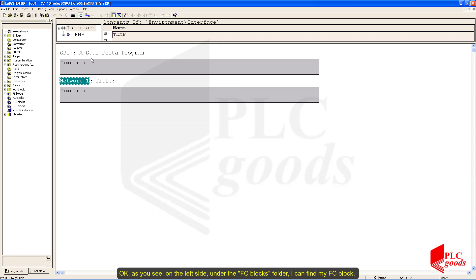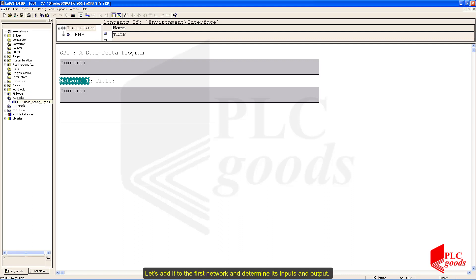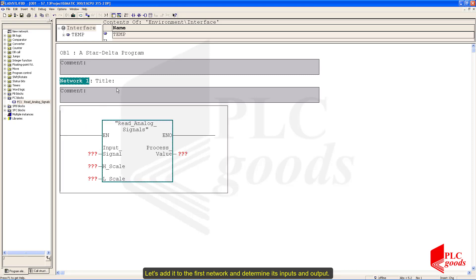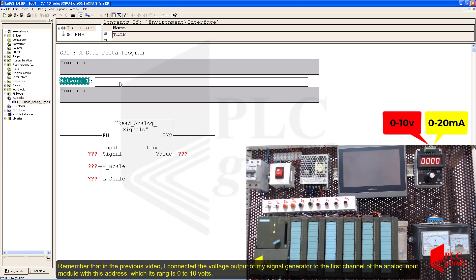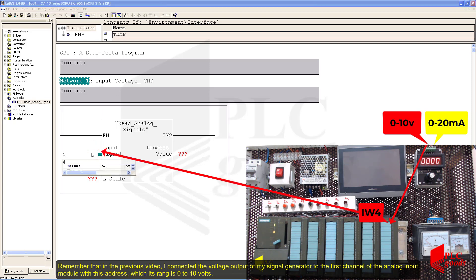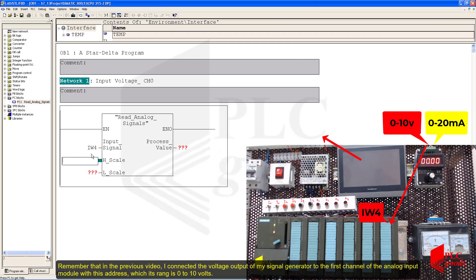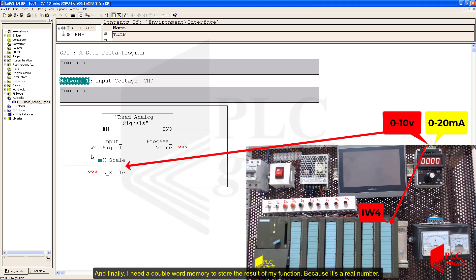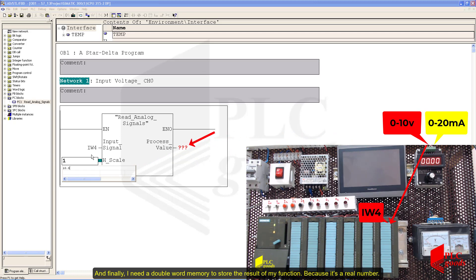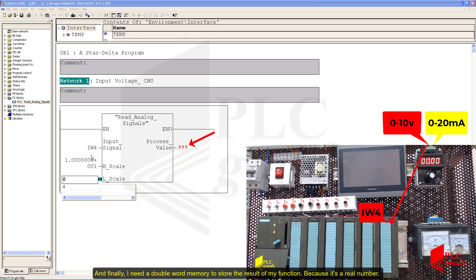As you can see, on the left side under the FC blocks folder, I can find my FC block. Let's add it to the first network and determine its inputs and output. In the previous video, I connected the voltage output of my signal generator to the first channel of the analog input module with this address, whose range is 0 to 10 volts. Finally, I need a double-word memory to store the result of my function because it's a real number.